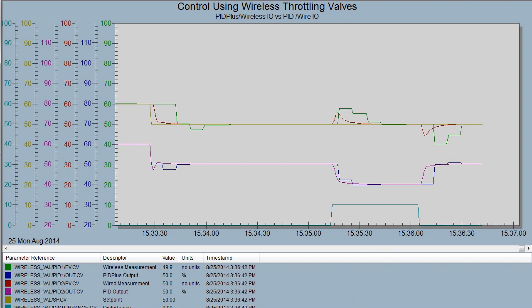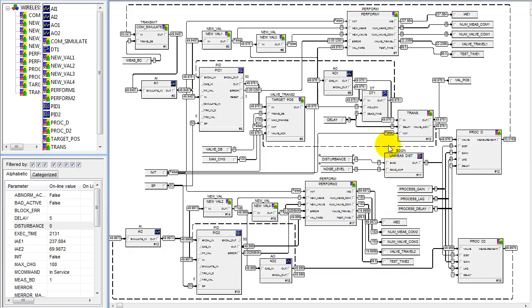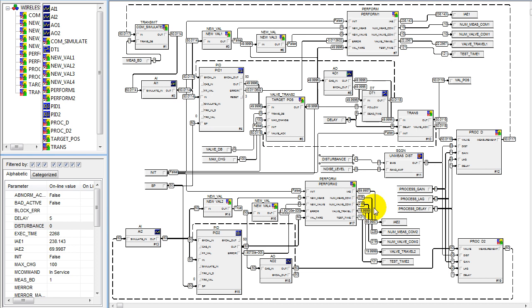We provide very comparable control using a wireless measurement and a wireless valve. The integral of absolute error is a little bit greater for the wireless, but in this particular case we only used 9 communicated values versus over 200 for the wired. This demonstrates the power of PID Plus and the time to apply command, and how it is used with a wireless valve to provide very effective control using both wired and wireless measurements. We hope this exercise has been helpful in understanding how the new time to apply command works.